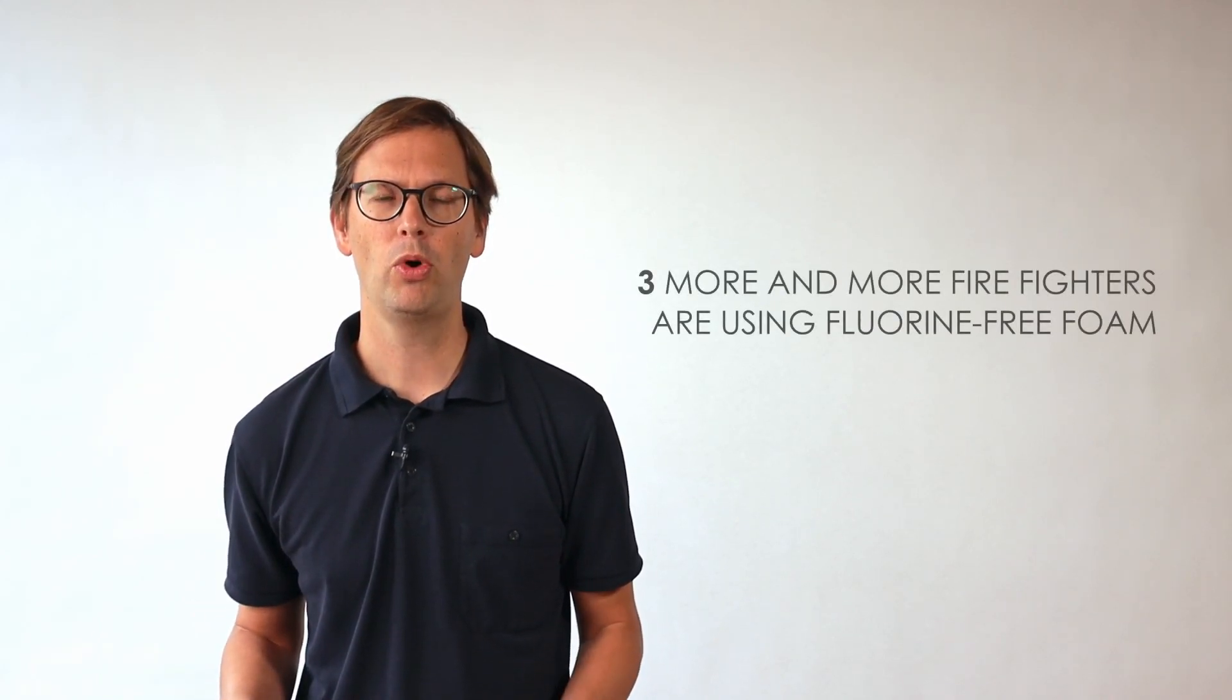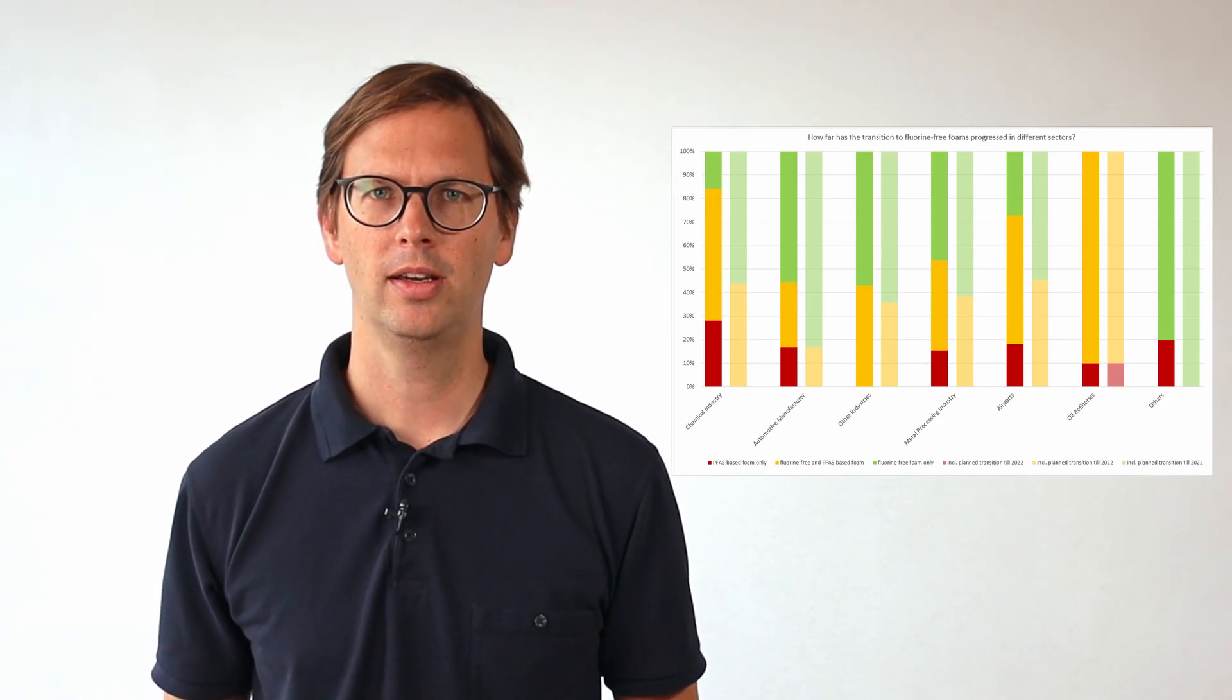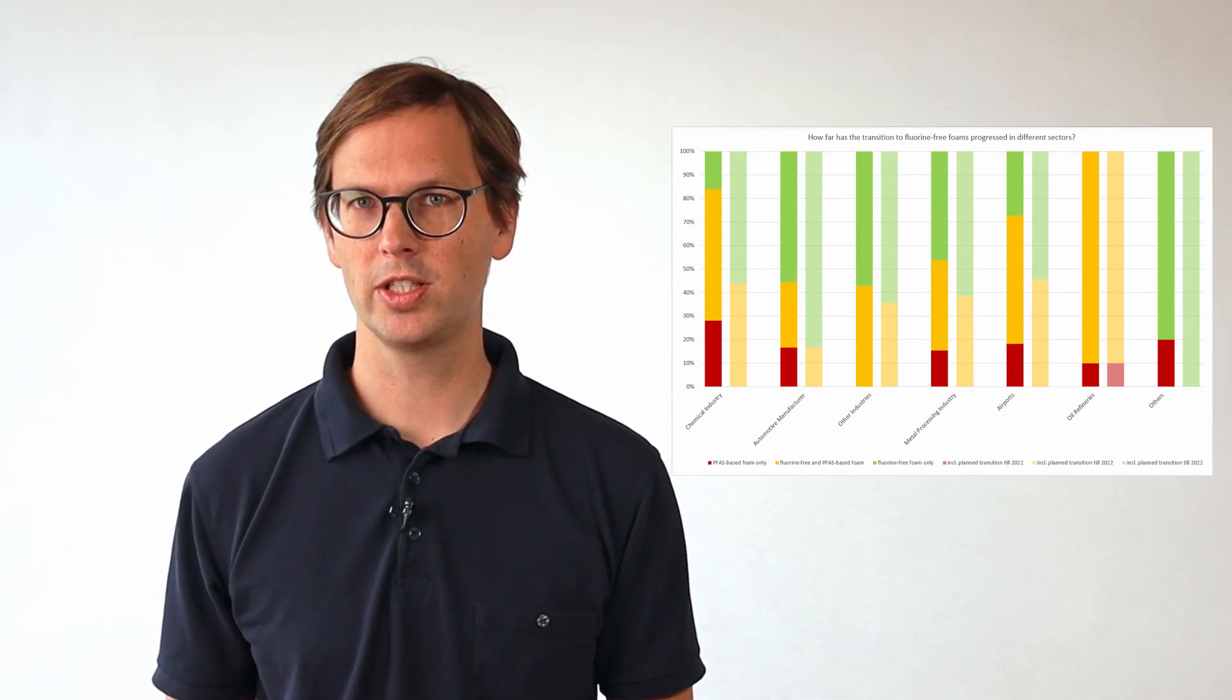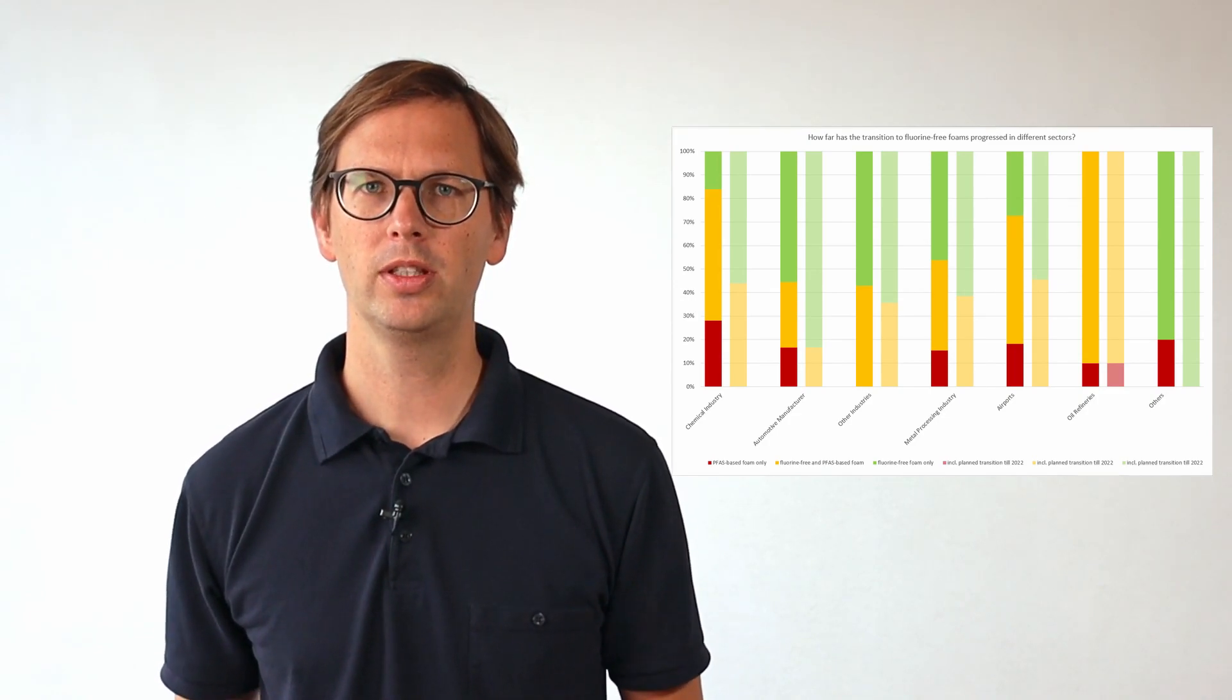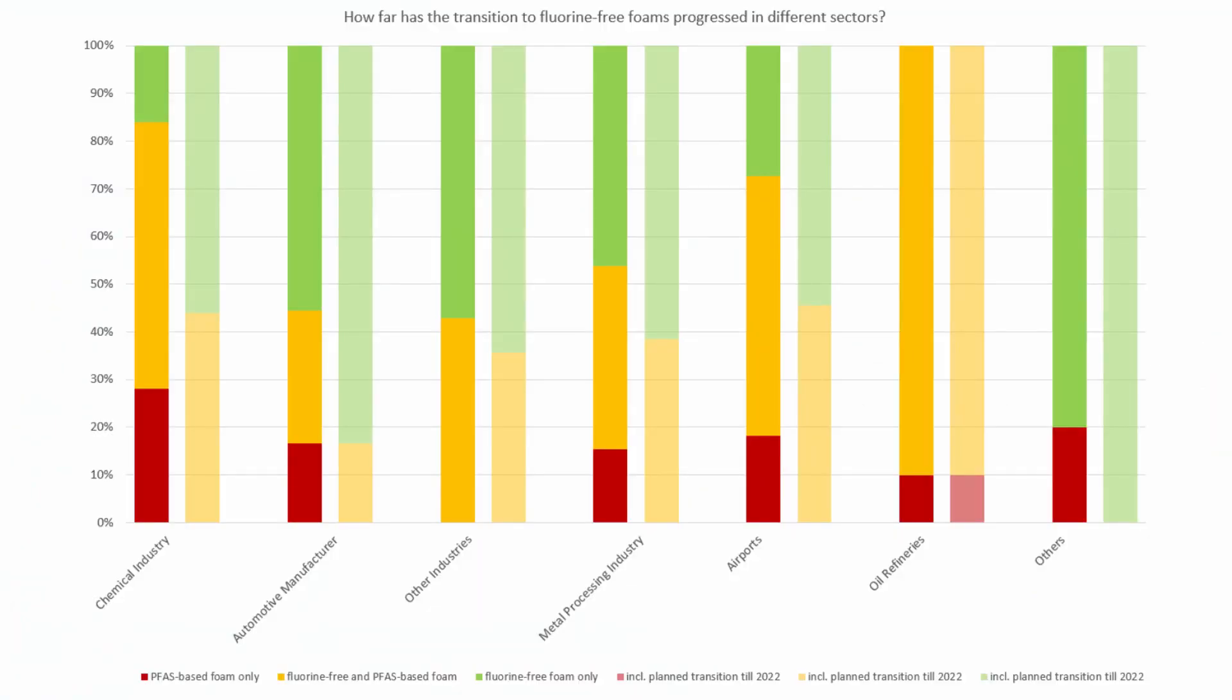And the third sign why a future ban on fluorine-based foam concentrates is likely: more and more firefighters are using fluorine-free foam. Here are the results of a survey that we carried out in summer 2020 among the industrial fire departments in Germany. Grouped into industries, you can see the current situation and the development if we include the planning for the next two years. Red means that only fluorine-containing foam is used. Yellow means the use of fluorine-containing and fluorine-free foam. And green that only fluorine-free foam concentrate is used.